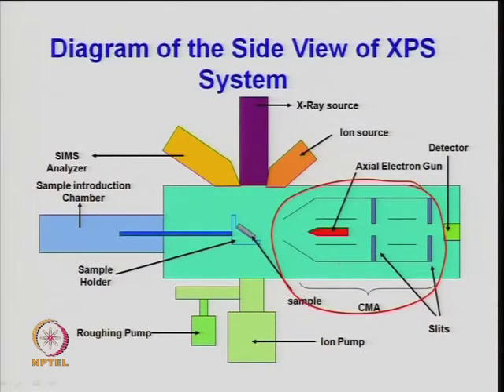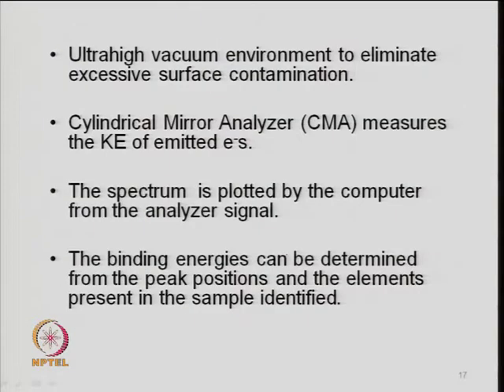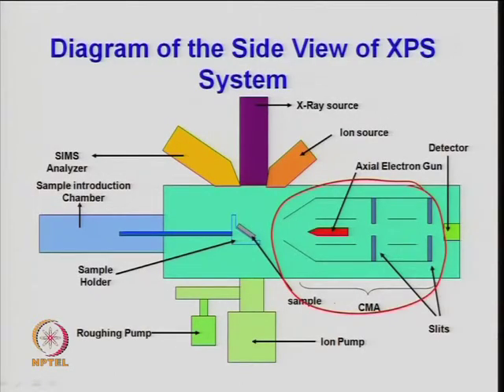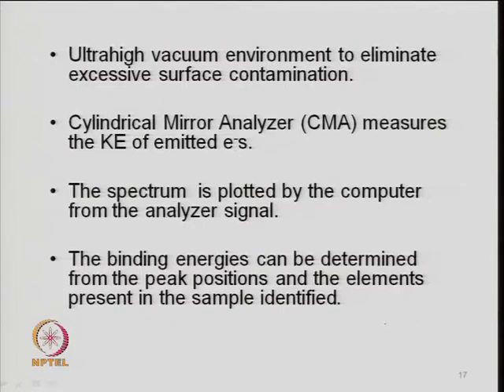After the first chamber at low vacuum, the sample is introduced into the second chamber where ultra-high vacuum exists. An ion pump and roughing pump create the vacuum in the system. Then the electrons are measured for kinetic energy after the beam hits. Ultra-high vacuum environment is needed to eliminate excessive surface contamination, since it is a very surface-sensitive technique. A cylindrical mirror analyzer (CMA) measures the kinetic energy of the emitted electrons.